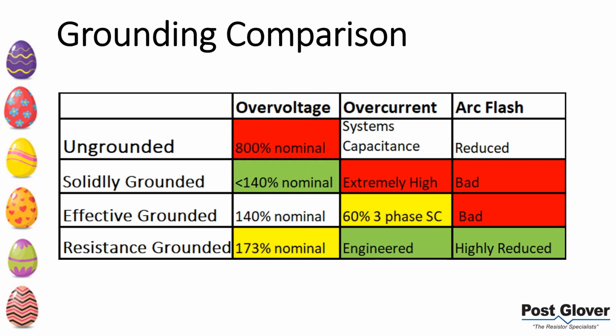Solid ground is kind of the opposite. I didn't have an exact number on the voltage, but essentially it's the lowest of all the comparison. And your overcurrent, just obviously by design, is designed this way. It's designed so you can have an extremely high current with relays able to see it very easily and trip offline as fast as possible. So by design, it's extremely high. And because of that, the arc flash is bad as well.